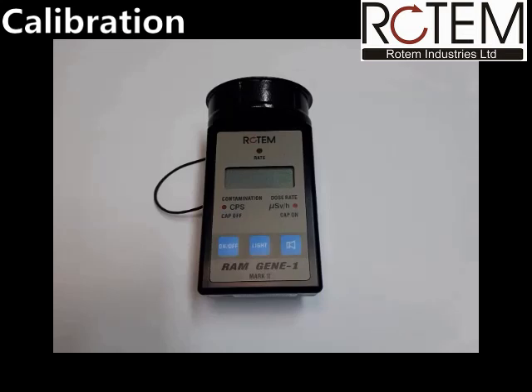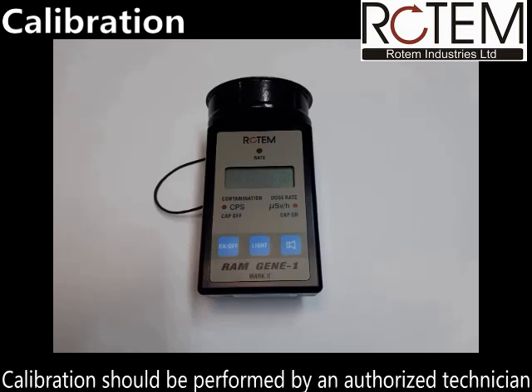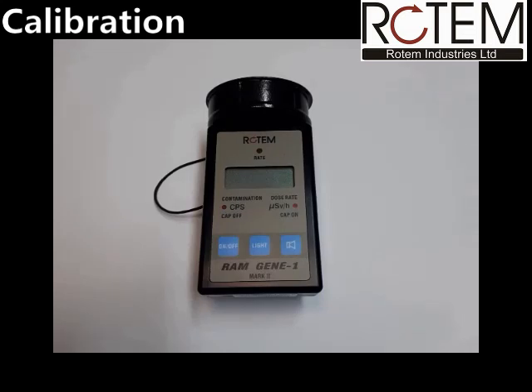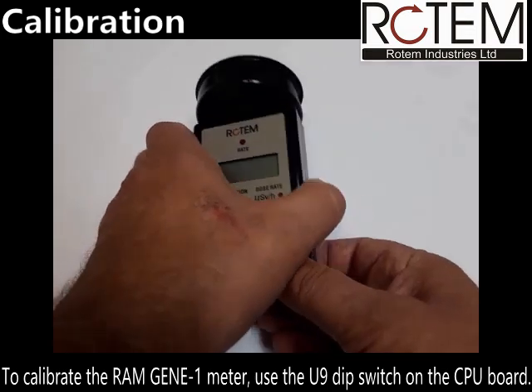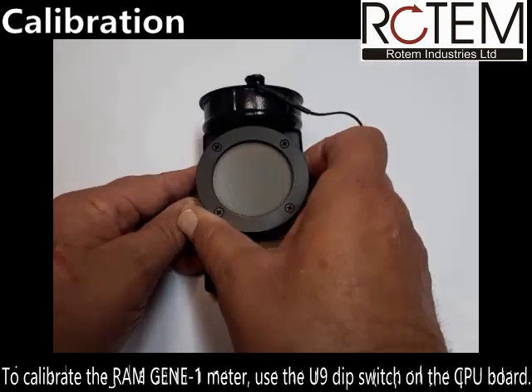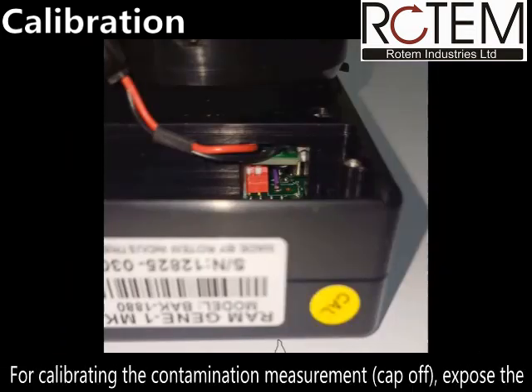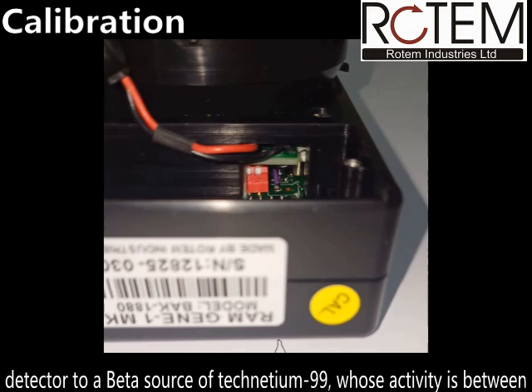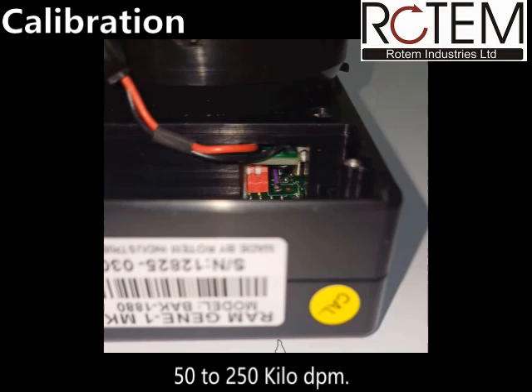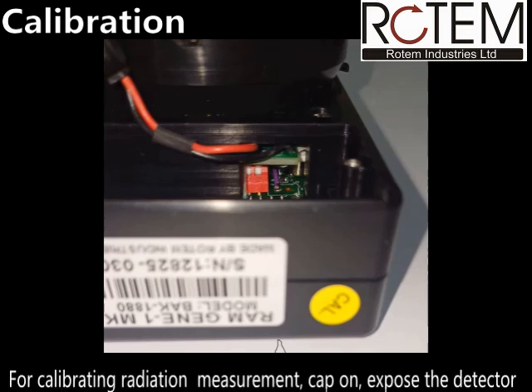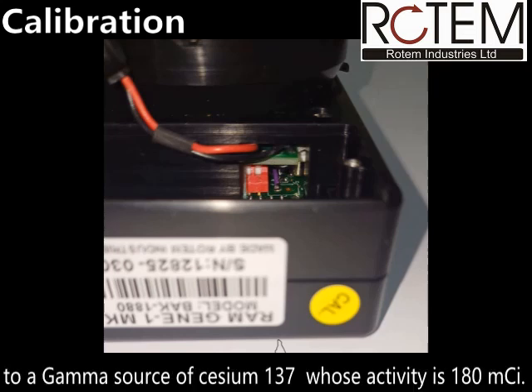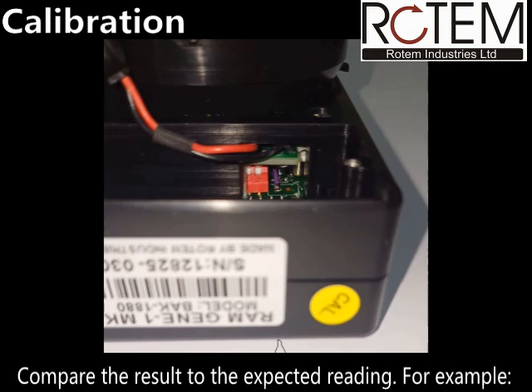Calibrating the RAM Gene 1. Calibration should be performed by an authorized technician. To calibrate the RAM Gene 1 meter, use the U9 dip switch on the CPU board. For calibrating the contamination measurement, cap off, expose the detector to a beta source of technetium-99, whose activity is between 50 to 250 kDpm. For calibrating radiation measurement, cap on, expose the detector to a gamma source of cesium-137, whose activity is 180 millicurie. Compare the result to the expected reading.